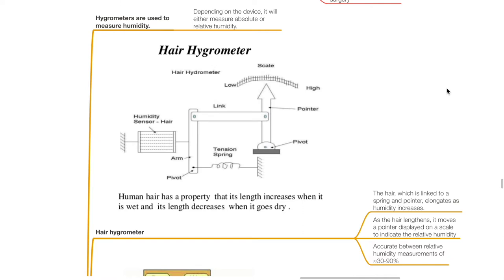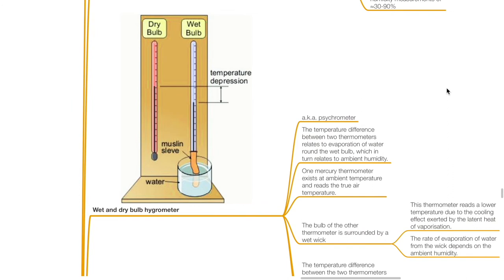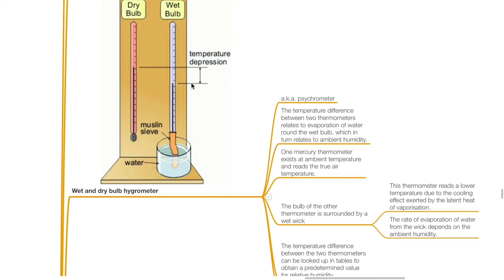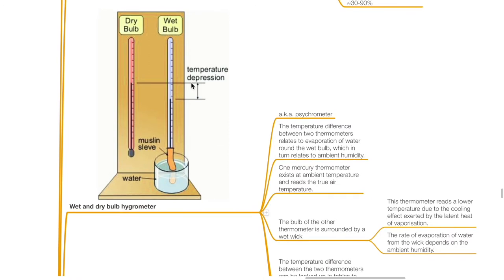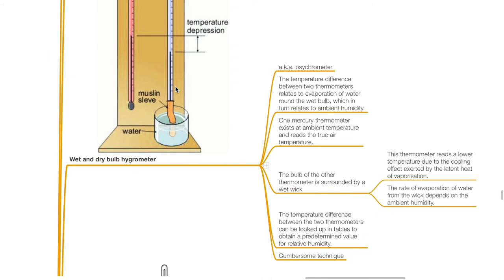The wet and dry bulb hygrometer, also known as the psychrometer: the temperature difference between the two thermometers relates to the evaporation of water around the wet bulb, which in turn relates to ambient humidity. One mercury thermometer exists at ambient temperature and reads the true air temperature. The bulb on the other thermometer is surrounded by a wet wick, which reads a lower temperature due to the cooling effect of the latent heat of vaporization. The rate of evaporation from the wick depends on ambient humidity, and the temperature difference between the two thermometers can be looked up in tables to obtain relative humidity. This is a cumbersome technique.